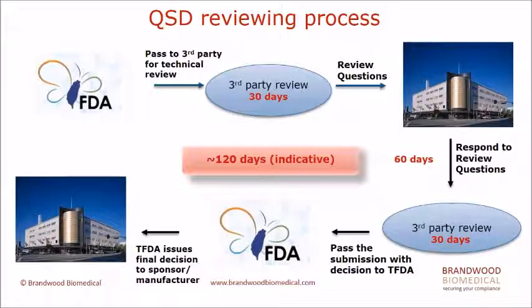Once the response submitted to the third party, they will review and provide decision back to Taiwan FDA. Taiwan FDA then do a final review and provide decision to the manufacturer. So the overall Taiwan FDA indicative reviewing timeline is 120 days for QSD applications. This timeline does not include any time spent to prepare the response to any review questions. In practice, the reviewing timeline is heavily dependent on the workload and resource at Taiwan FDA. Given our current experience, there are backlog of applications at Taiwan FDA, so the minimum timeline to get approval, we're looking around 6 to 9 months minimum. For renewal QSD applications, we will suggest to submit the application sooner than later.